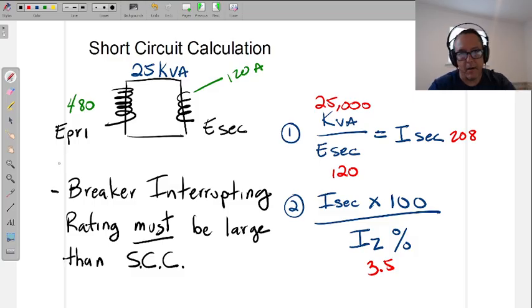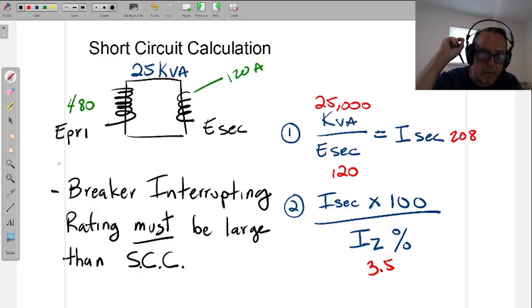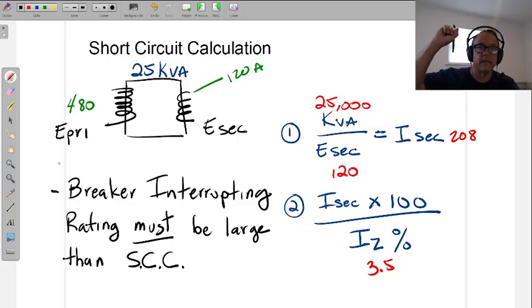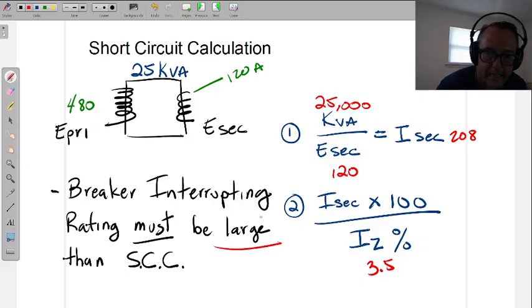So let's say, for example, I came up with a short circuit calculation of 28,000 amps, then 30 kA, 35,000, 40,000, anything, as long as it's larger. Now, of course, price comes into effect, so they're kept fairly close to what the short circuit calculation is. But again, larger is the key, not equal to.